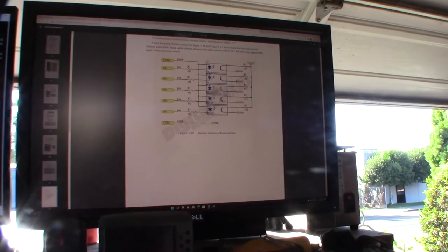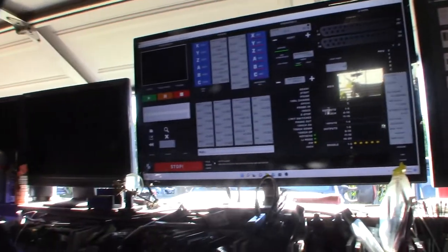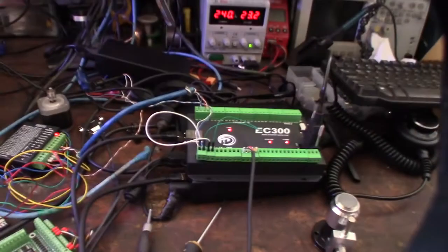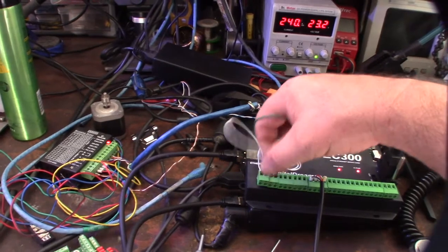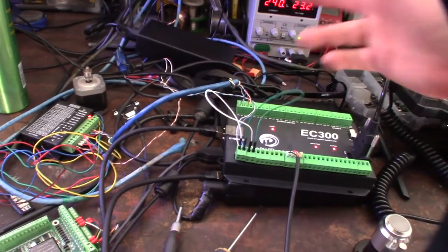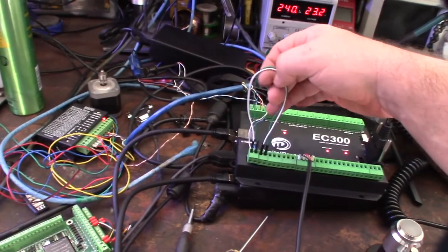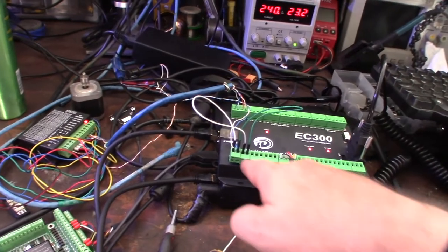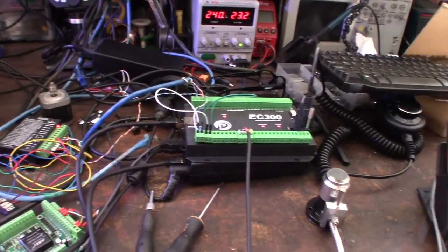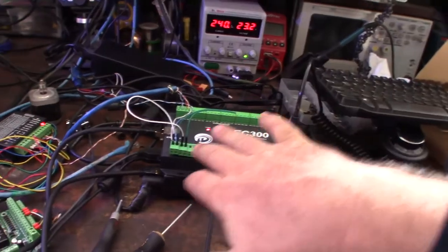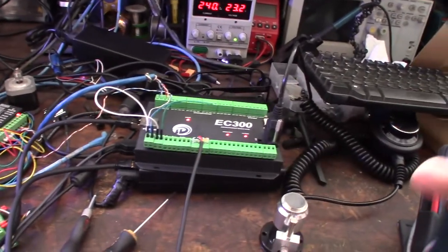Alright, so now I got a ground, power back on. I think I definitely improved the manual. So I looked more at their diagram of the input circuit, and you do need the COM plus and the COM negative. So I need to run a jumper from the positive side to the negative side. I mean, the problem is you're not isolating the power. So ideally, you'd want to make a second power supply that was actually feeding this separate thing here. That way you're preventing that.